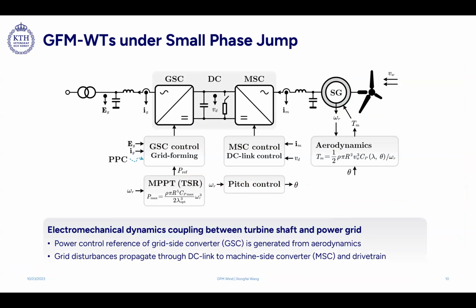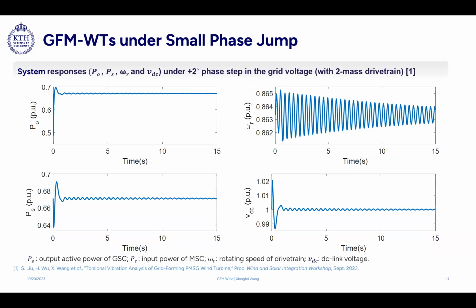As I mentioned, if we consider the energy source limit, for example the wind turbine, this is the second type of grid forming wind power plant. Here, we have to respect the energy source limit. In this case, we regulate the DC link voltage using the machine side converter, and we use the grid side converter to perform the grid forming capabilities. In this way, all the grid disturbances or power dynamics are coupled to the aerodynamics of the wind turbines.